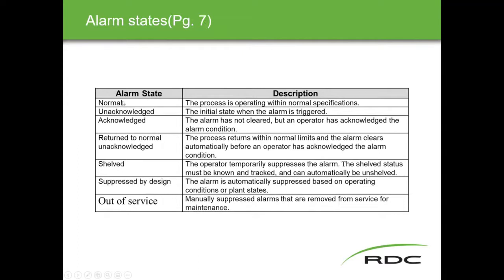Different alarm states include: normal, unacknowledged, acknowledged, return to normal unacknowledged, shelved, suppressed by design, and out of service. 'Return to normal unacknowledged' means the process went into an alarm state — say a high level — but then came back down and cleared itself. 'Shelved' means the operator temporarily suppresses the alarm, which is somewhat dangerous and must be documented. 'Suppressed by design' and 'out of service' are relatively self-explanatory.